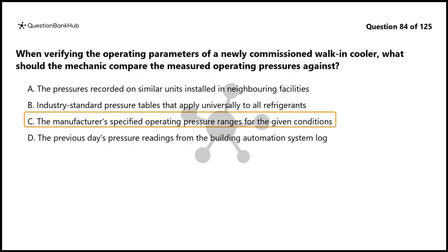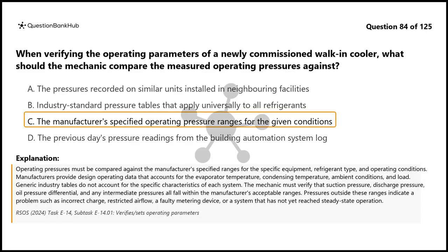The correct answer is C. Operating pressures must be compared against the manufacturer's specified ranges for the specific equipment, refrigerant type, and operating conditions. Manufacturers provide design operating data that accounts for the evaporator temperature, condensing temperature, ambient conditions, and load. Generic industry tables do not account for the specific characteristics of each system. The mechanic must verify that suction pressure, discharge pressure, oil pressure differential, and any intermediate pressures all fall within the manufacturer's acceptable ranges. Pressures outside these ranges indicate a problem such as incorrect charge, restricted airflow, a faulty metering device, or a system that has not yet reached steady-state operation.